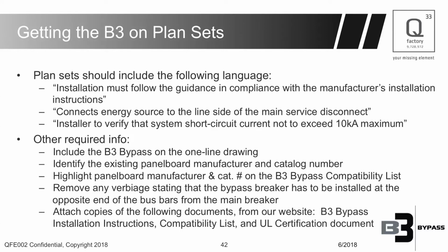Okay. And then we recommend that you include the following information. Include on your one line the B3 ByPass. Show it as part of the installation, as I showed early on in that one line at the beginning of the presentation. Identify the existing panel board, manufacturer and catalog number. And then what we recommend that you do, on the compatibility list, circle it so that they see that it's on there. Again, let's avoid any questions, any trips back to that office. You don't want to go back to the counter. Just take a few minutes, circle it, have your plan people circle it before you submit it.